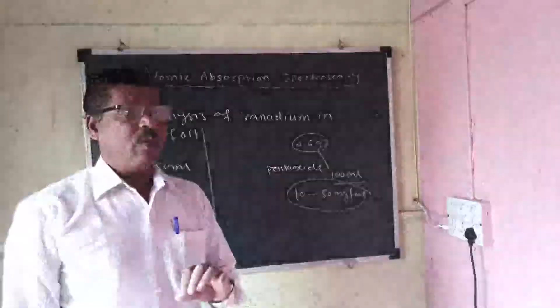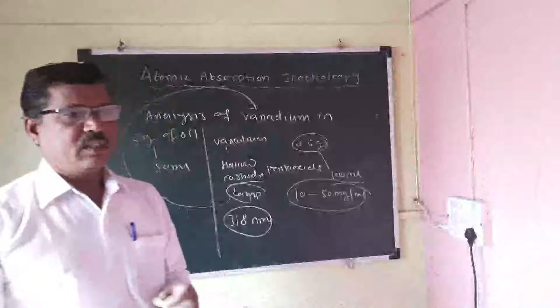Select the resonance line wavelength for vanadium, which is 318 nanometer. This is the specific wavelength of vanadium. Adjust the gas controls to give a fuel rich acetylene nitrous oxide flame, and aspirate successively into the flame the solvent blank, the standard solutions, and finally the test solution. In each case, record the absorbance reading to plot the calibration curve and determine the vanadium content of the oil. Okay, thank you.